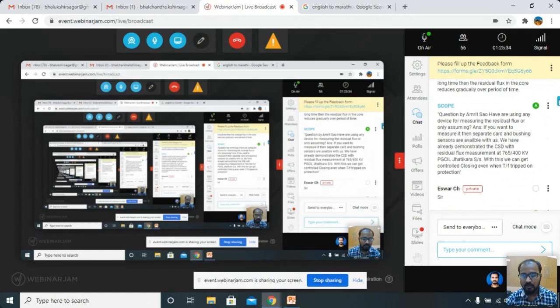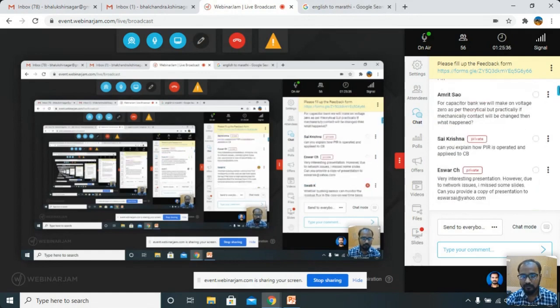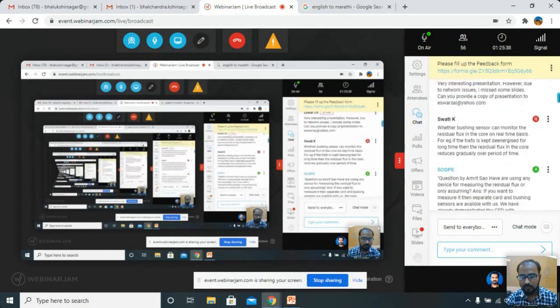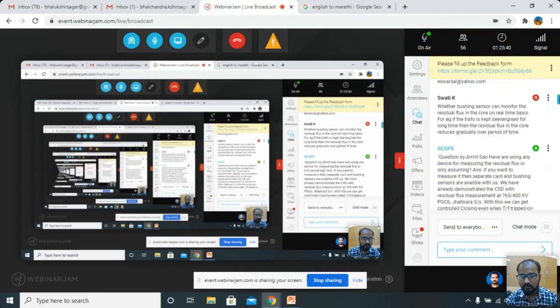Balchandra, there is a question from Swati K. Whether the bushing sensor can monitor the residual flux in the core on a real-time basis. Example given, if the transformer is kept de-energized for a long time, then the residual flux in the core reduces gradually over a period of time. So you can respond to that.